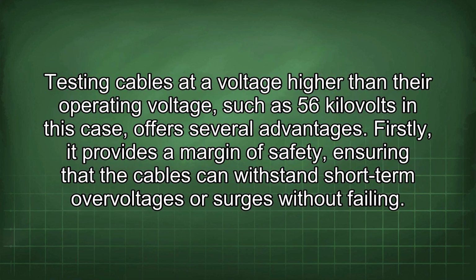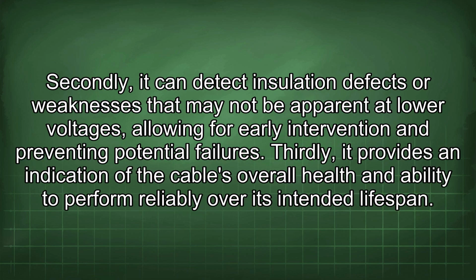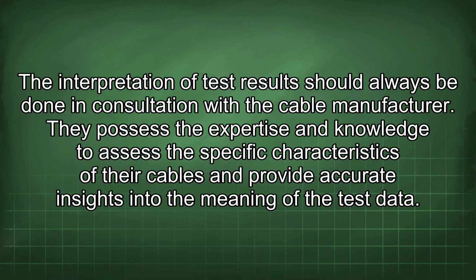Testing cables to a voltage higher than their operating voltage, such as 56 kV in this case, offers several advantages. Firstly, it provides a margin of safety, ensuring that the cables can withstand short-term overvoltages or surges without failing. Secondly, it can detect insulation defects or weaknesses that may not be apparent at low voltages, allowing for early intervention and preventing potential failures. Thirdly, it provides an indication of the cable's overall health and ability to perform reliably over its intended lifespan. The interpretation of test results should always be done in consultation with the cable manufacturer. They possess the expertise and knowledge to assess the specific characteristics of their cables and provide accurate insights into the meaning of the test data.